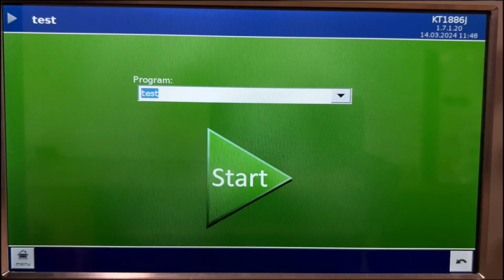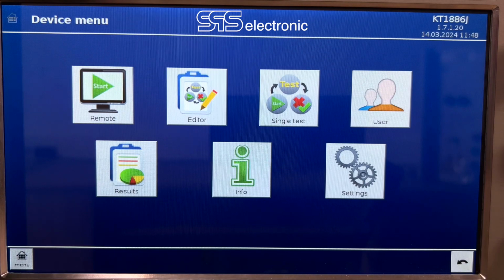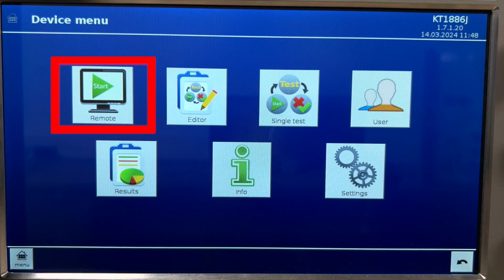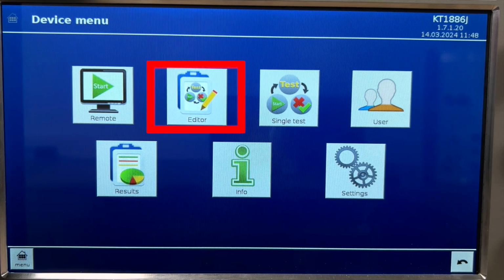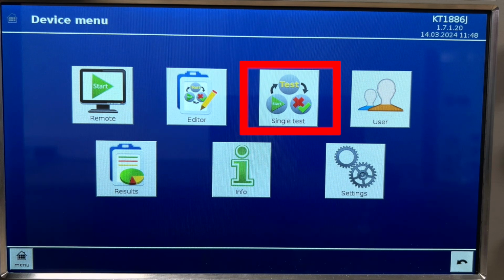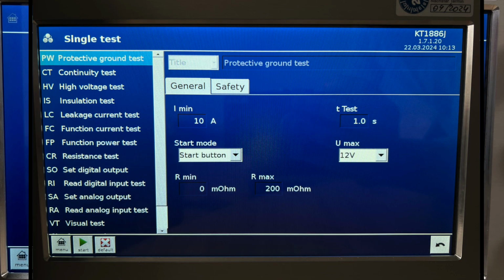Now we can test. From main screen, we can go to menu, where we can see all the functions. First, we got remote option for remote control of your device via software or PLC. Second, we got editor option, where we can make complete test programs. Next to it, we have a single test, where we can find all the tests a tester can do, like protective ground test, continuity test, high voltage AC/DC test, insulation test, leakage current test, function tests, and many more.